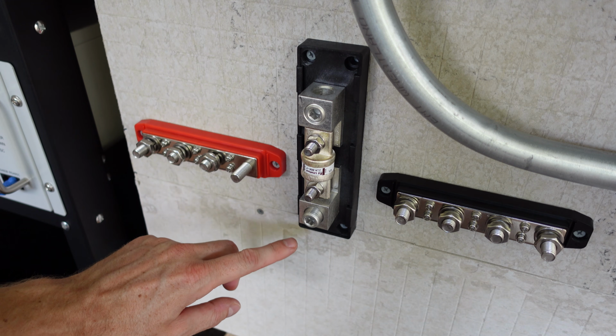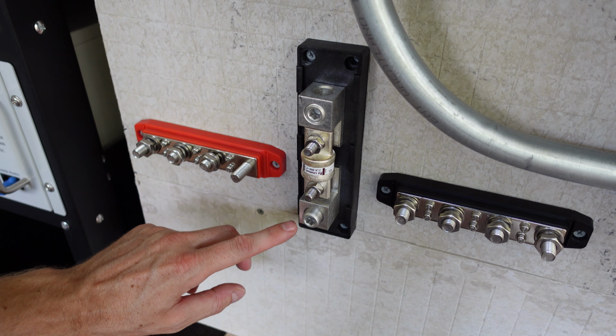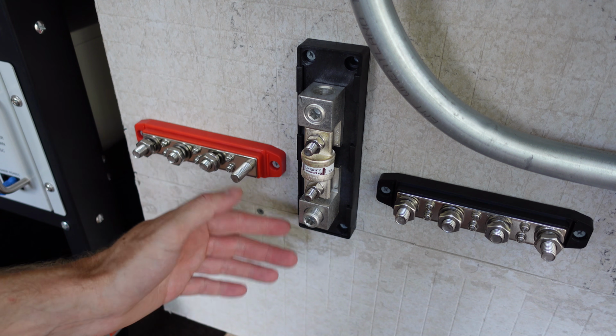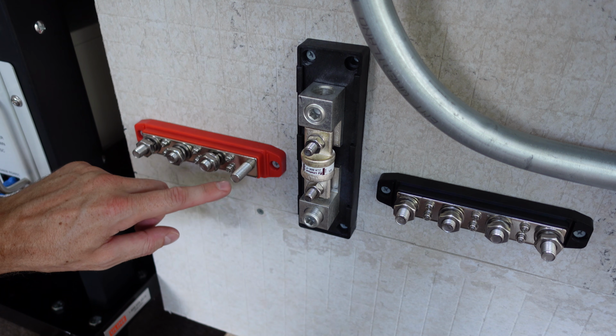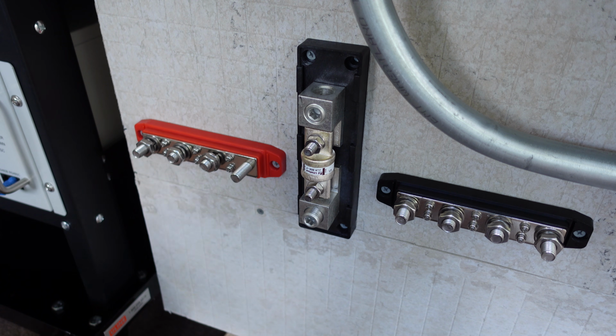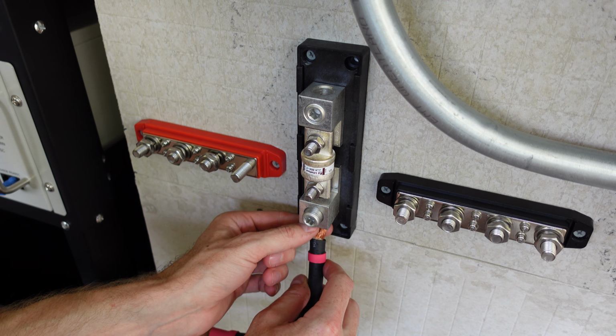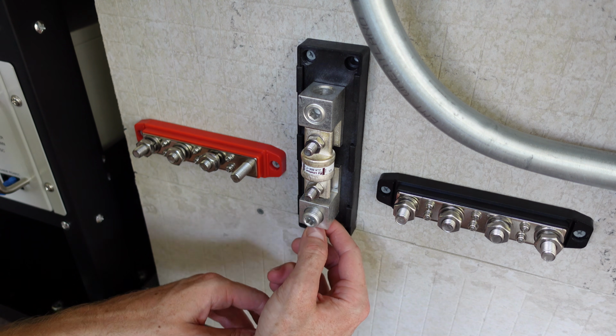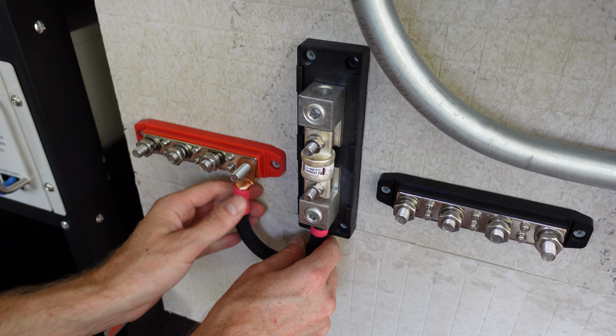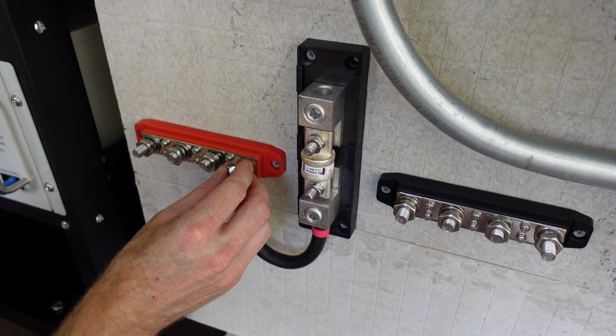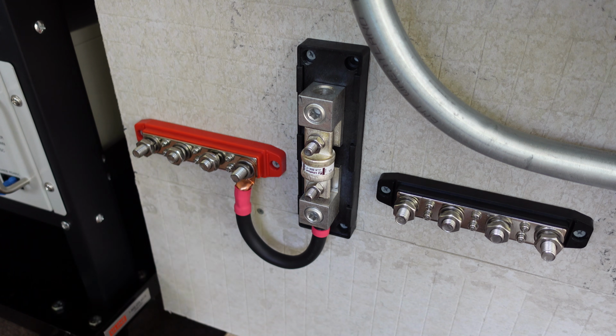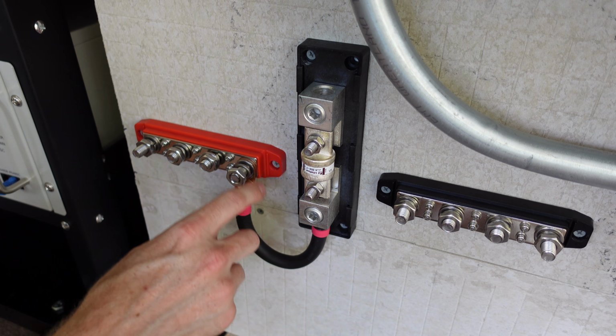So for making the connections on the fuse block, we've got an 8mm hex bolt, or Allen head, however you want to call it. And then we've got a 17mm nut on the bus bar. So I'm just going to insert the stranded wire directly into the fuse block. The other end will go on the positive bus bar. Then we've got a flat washer, a lock washer, and the 17mm nut.